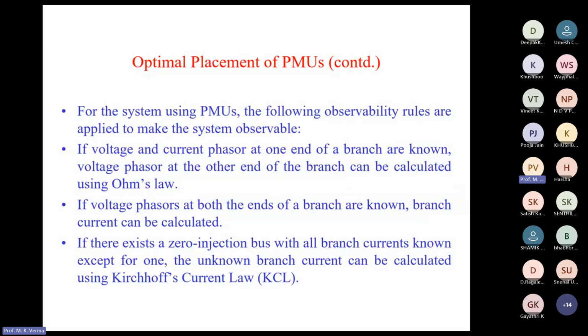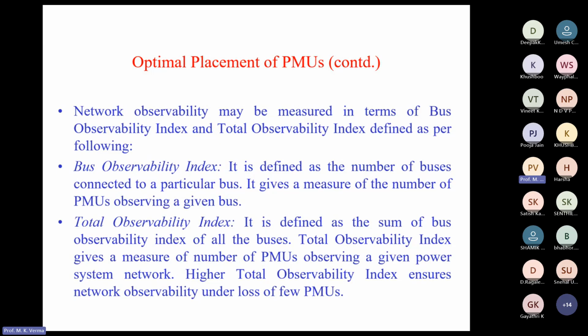These rules were adopted for minimizing the number of PMUs because if a PMU is placed at a certain bus, it can measure the voltage, current, and frequency at that bus. And if the bus is connected to another bus, then by Ohm's law, you can calculate the voltage drop in that line that is connected to the other bus. So no need of putting a PMU at the other bus. Now, if the voltage phasors at both ends are known, the branch current can be calculated. And if it is a zero injection bus, then we can calculate the currents in different branches connected to it by KCL. So that can minimize the number of PMUs to be placed.